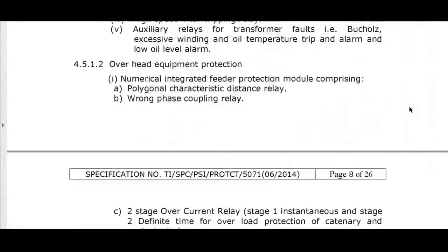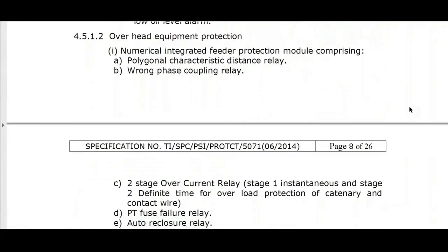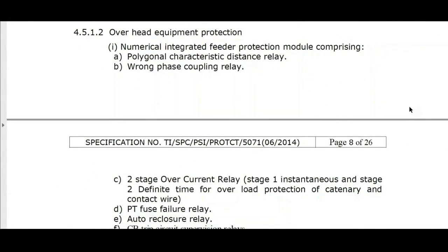So next is, what are the list of protections required for overhead line? Feeder protection, polygonal characteristics distance relay. Okay, so earlier in the presentation we saw parallelogram characteristics. A parallelogram is also a polygonal characteristics. So you need a distance relay. It's nothing but a non-unit relay, which we have already seen. Measured impedance and set impedance has to be compared and protected.